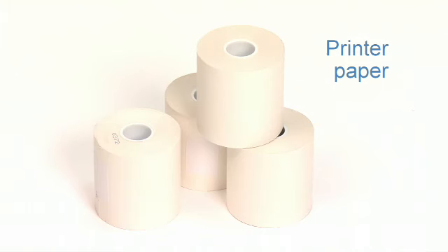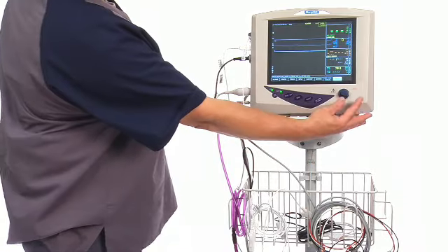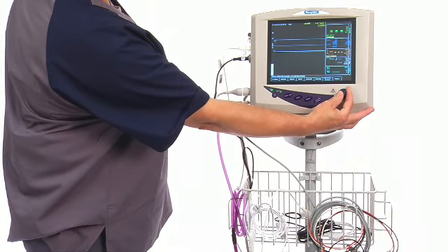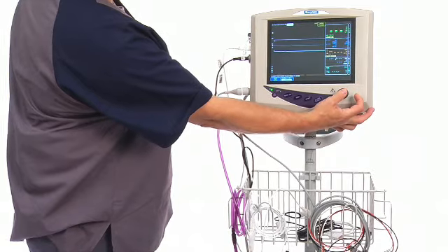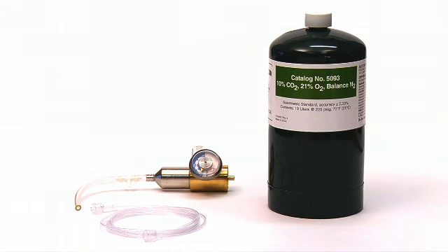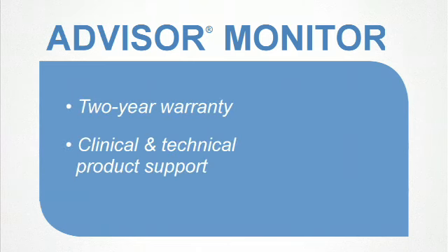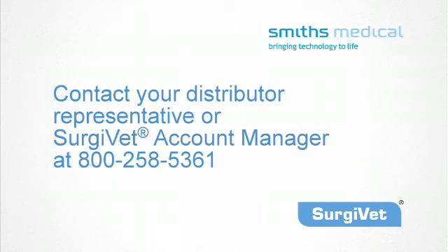The Advisor Monitor's recommended periodic maintenance can easily be performed in the field by the end user. Accessories can be changed out as needed and ordered through Smith's Medical or authorized veterinary distributors. A specified CO2 calibration kit is required if a CO2 module is purchased. The Advisor Monitor comes with a 2-year manufacturer's warranty, and all SurgiVet products come with lifetime unsurpassed clinical and technical product support. For more information, contact Smith's Medical at 800-258-5361.